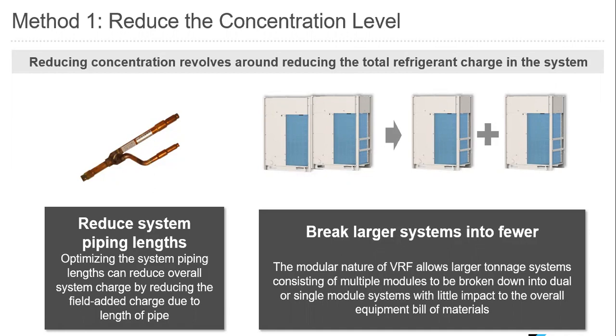So a good way to design a system is actually to have single modules, and maybe here and there have some dual modules. So this helps us reduce that refrigerant concentration limit, partly because it's going to help us reduce the overall system piping lengths. So by optimizing the module sizes and the piping lengths, we can actually reduce the amount of refrigerant that we're going to send to a space.